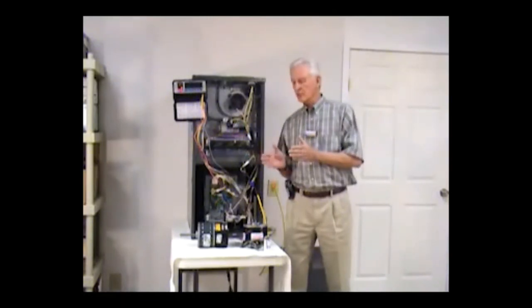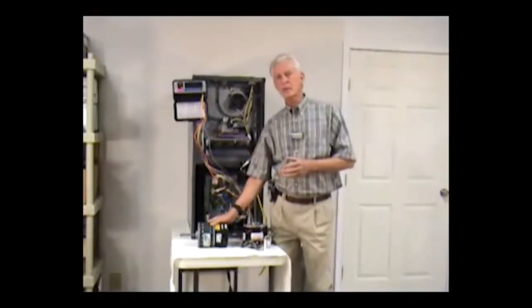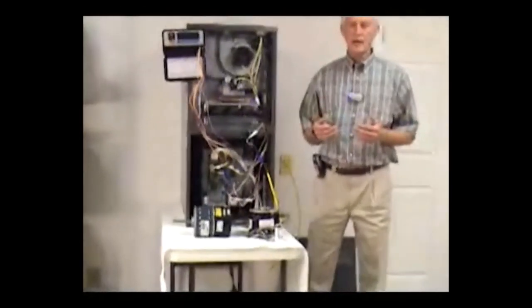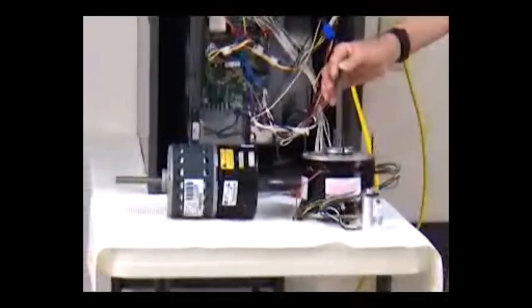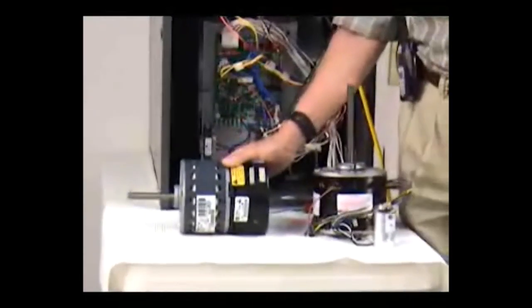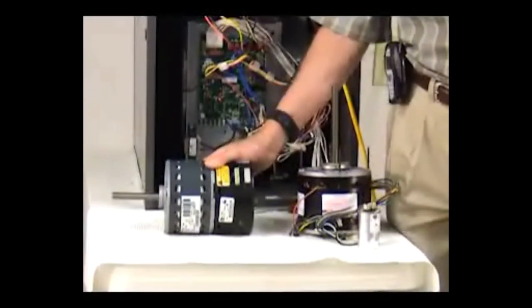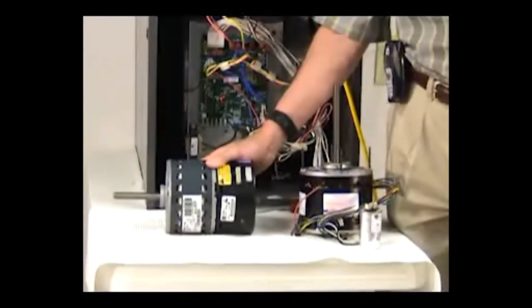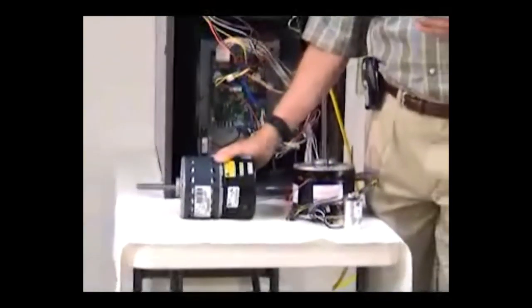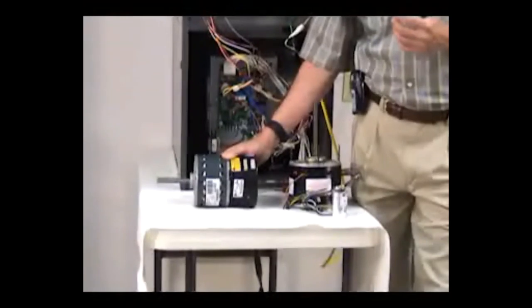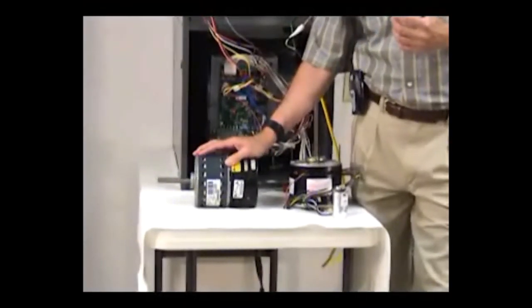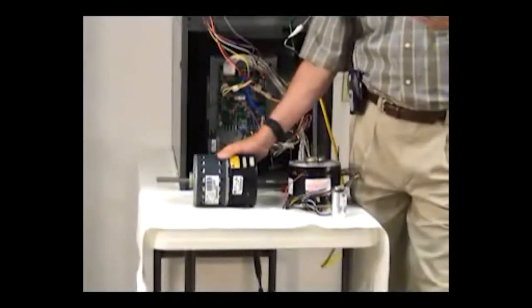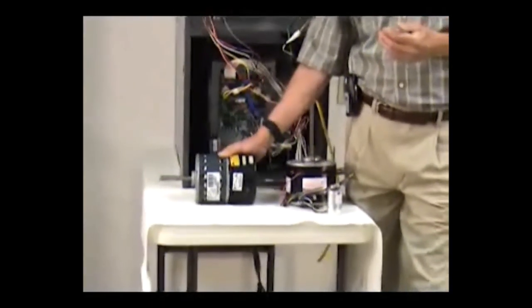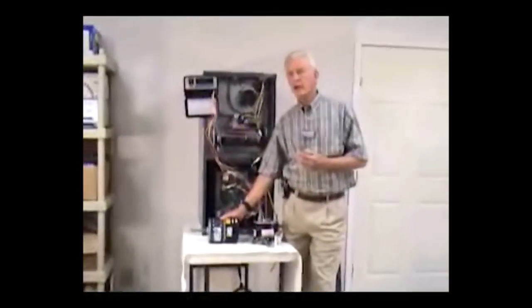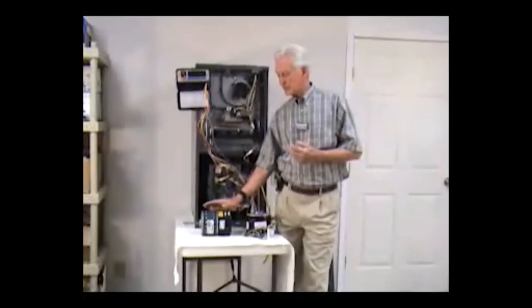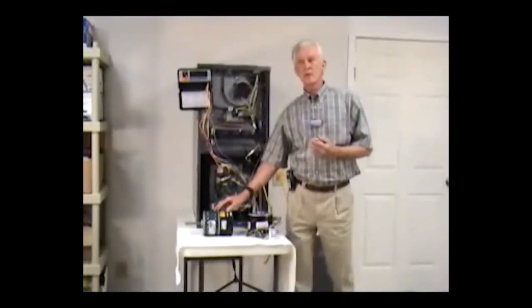So now what we're going to do is go to the ECM motor and say external static pressures are starting off in a 0.3 range, and at the 0.3 range our amperage draws on this motor are extremely low, which makes it very, very efficient, which allows the manufacturers to pick up additional efficiencies with their piece of equipment, strictly through the fact that the motor itself is drawing much lesser amperage. However, for us to accomplish that, we do have to stay in the lower ranges of external static pressure, 0.3 to 0.5.